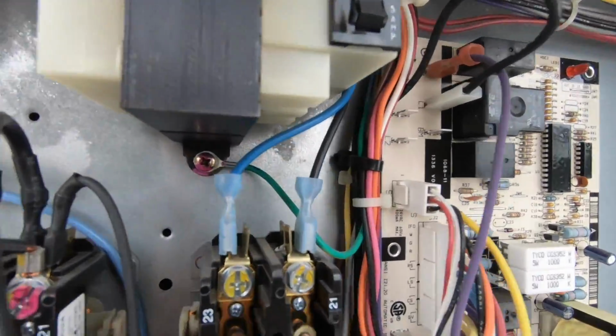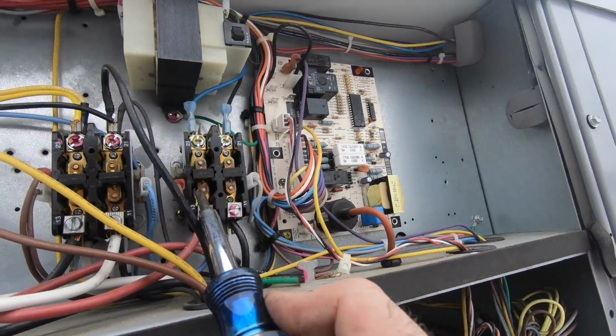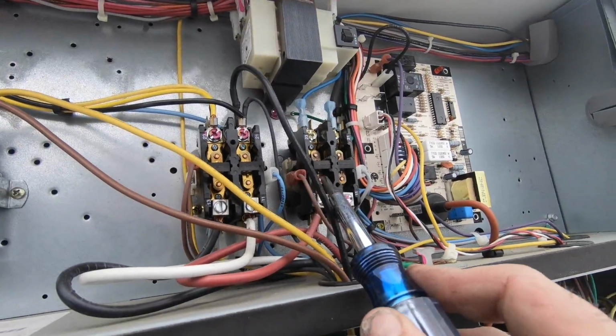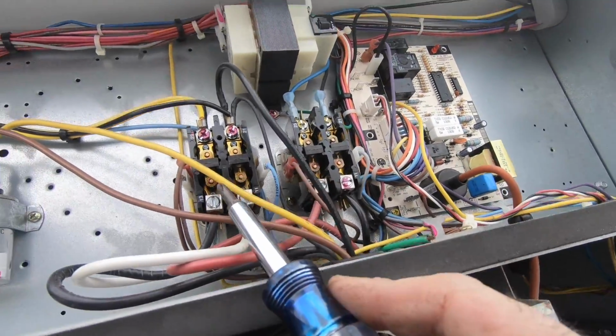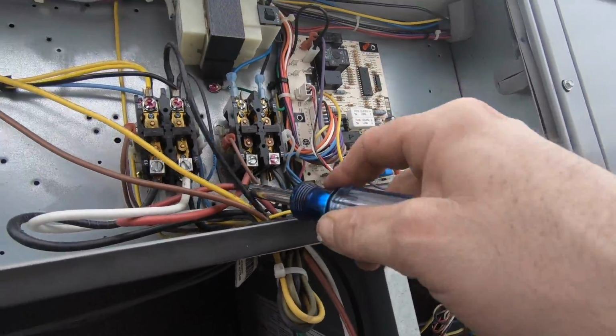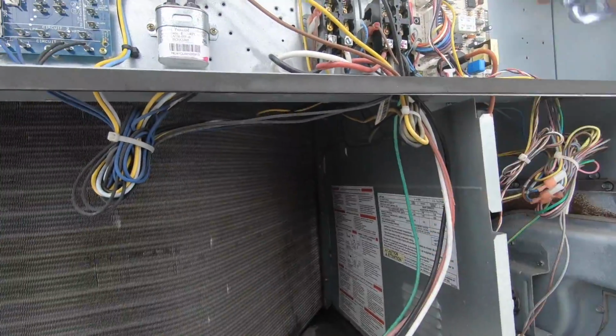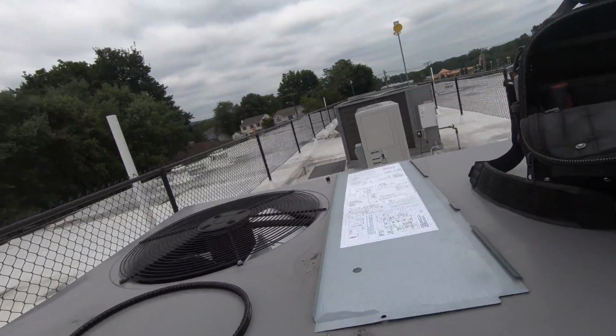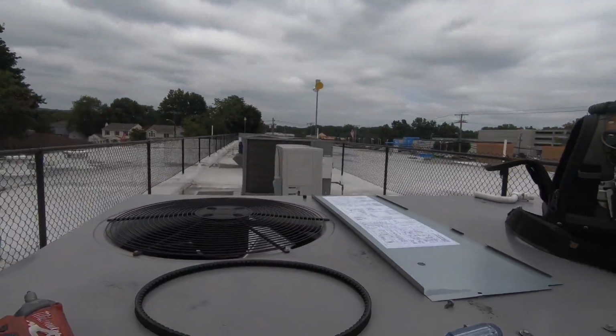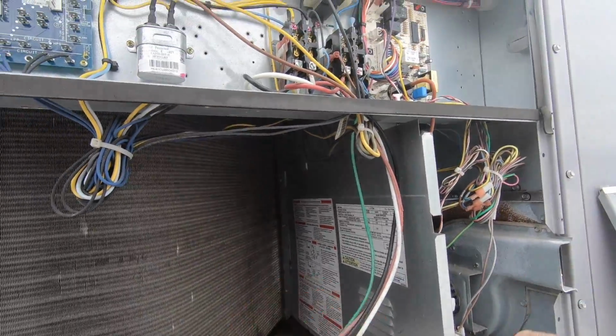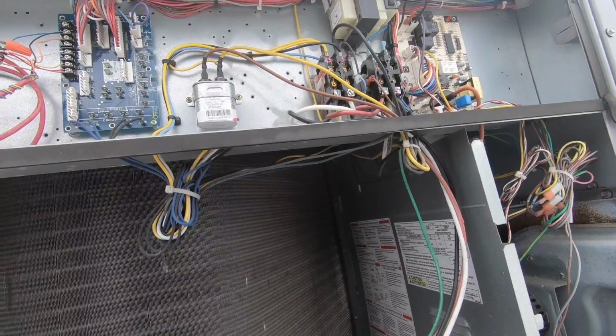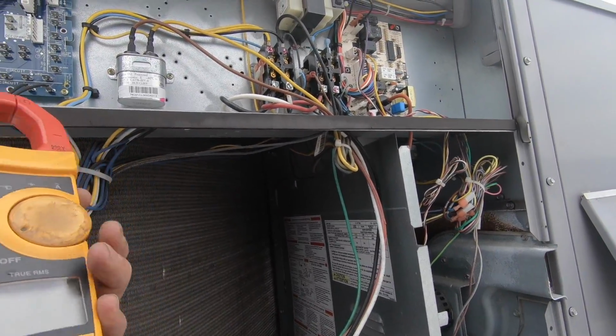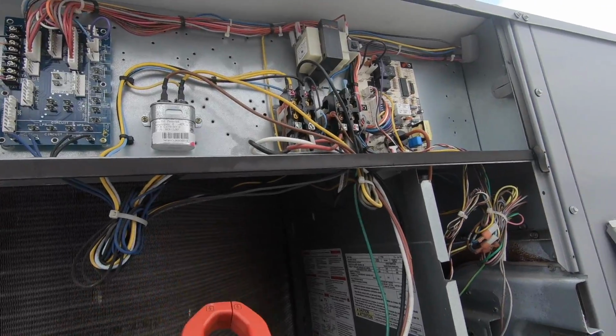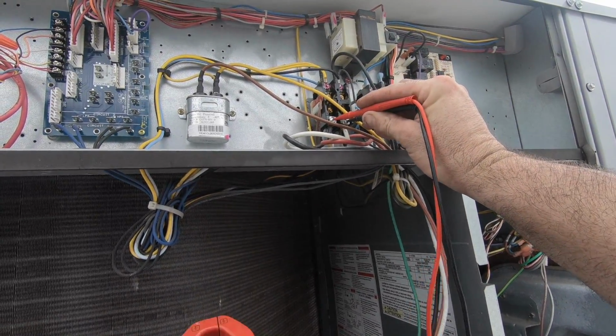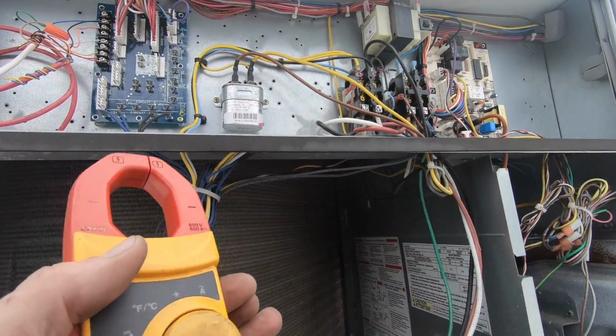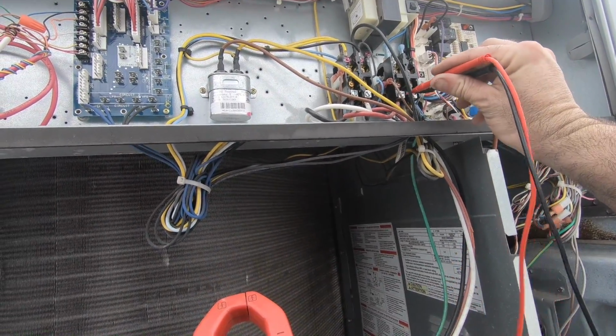I like to make sure my contact points, nothing brown, black, like this is getting a little discolored, but I'll live with this because underneath it looks good. But this one will start to darken. I'll make sure that's tight. Power is off. Always confirm with your meter. I've had blades and disconnects break. And you don't want to get hit with some voltage. Oh, I got a red wire. I hope I didn't trigger the smoke when I shut this thing off. 0 volts. Okay, so I don't have anything coming in, so I'm good to go.